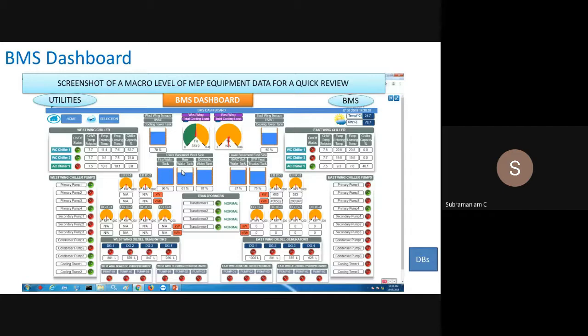And this is one sample dashboard for the entire building, for example, one BMS screen. If the operator comes and opens the screen, he can get to know what my cooling load is, what my tank water level is, what my DG tank level in the building is, whether I have day fuel for 1 day, or whether there is one tank having a problem. How many chillers are running, what is my chilled water set point, what is the leaving temperature. For example, here 7.7 degrees is the set point, 7.6 degrees is the leaving temperature. What is my chiller capacity? It is running at 62.7%. Why? Because the ambient temperature is only 24.7. You can see it on the right hand top corner of the screen.